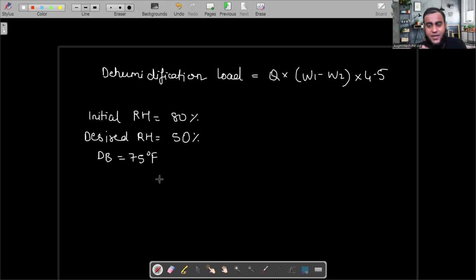So in the same way, you have to substitute. First calculate the W1 value. In the psychrometric software, you enter the 80% and 75%, and you will get the W1 value. In the same way, enter the desired relative humidity, and you will get W2. And airflow rate, same concept: volume of room in cubic feet times ACH divided by 60. You will get the Q value. Substitute, and you will get the dehumidification load, okay, in pounds per hour.